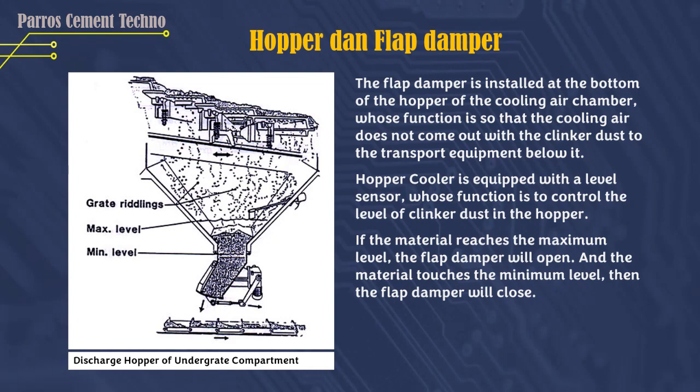Hopper and Flap Damper. The flap damper is installed at the bottom of the hopper of the cooling air chamber, whose function is to prevent cooling air from coming out with the clinker dust to the transport equipment below it. The hopper cooler is equipped with a level sensor whose function is to control the level of clinker dust in the hopper. When the material reaches the maximum level, the damper flap will open. When the material touches the minimum level, the flap damper will close.